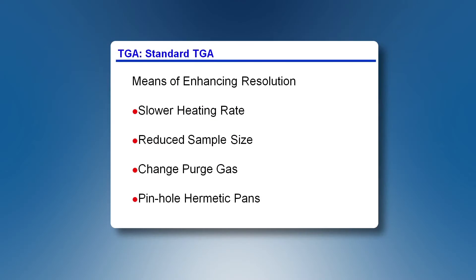In a standard TGA, in order to improve the resolution, typically we slow the heating rate, we reduce the sample size, we change the purge gas, or even we use hermetic pinhole pans. The most common approach is to slow the heating rate. The problem with that is that our experimental time will increase too much.